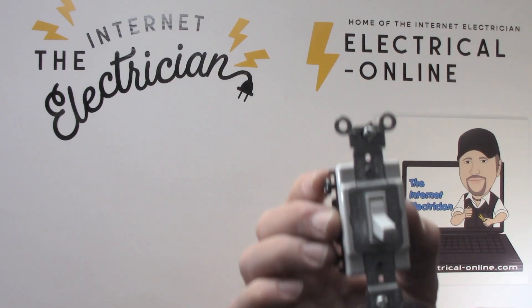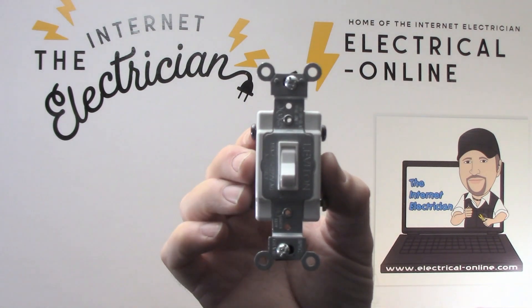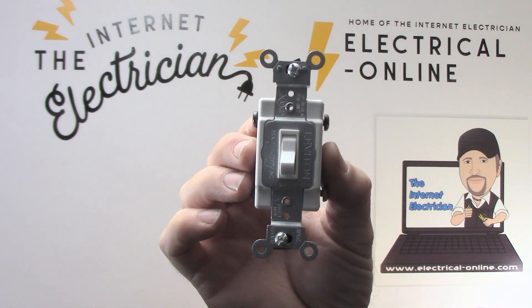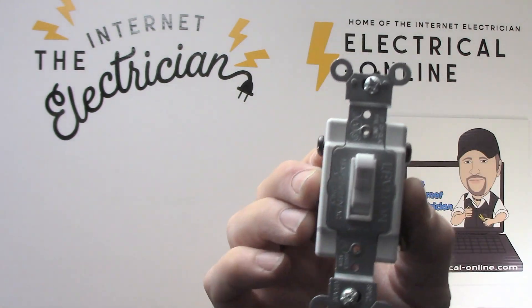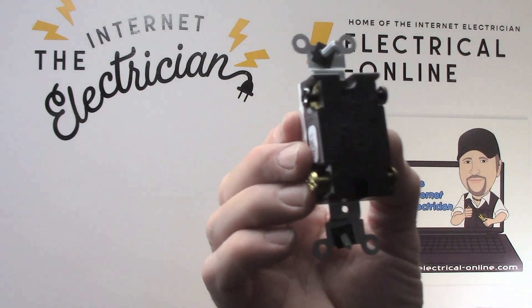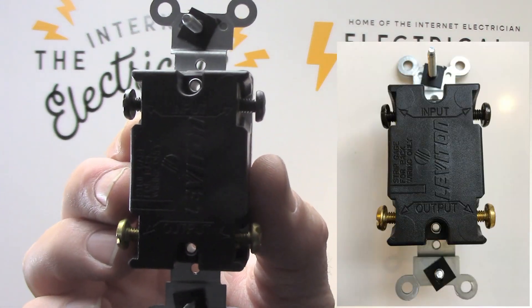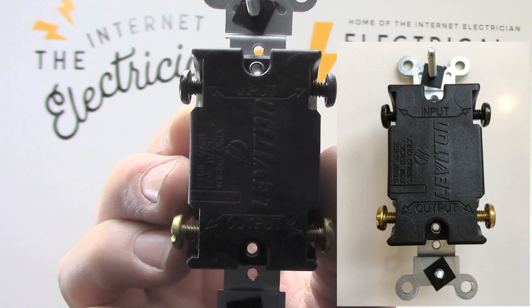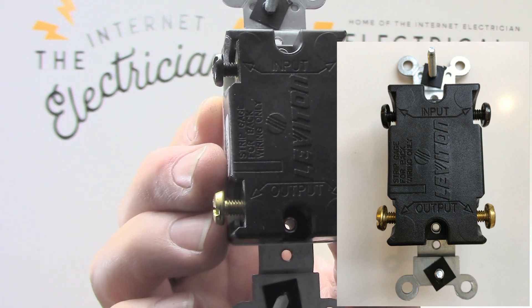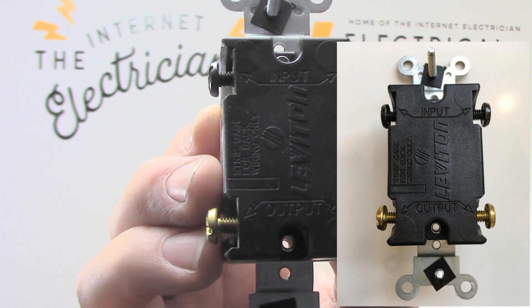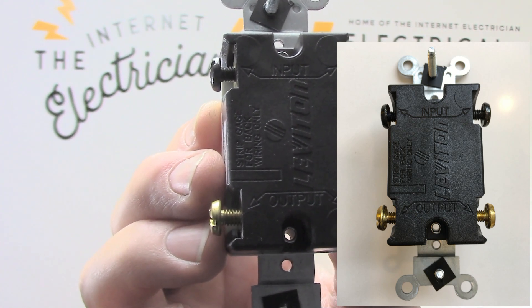So now let's take a close up look at the four way switch. As you see, there is no indication of on or off on the handle. No indication. And then looking at the back, we're going to go in for a nice close up. And you can see there. Input and output. As opposed to line and load on the double pole switch.